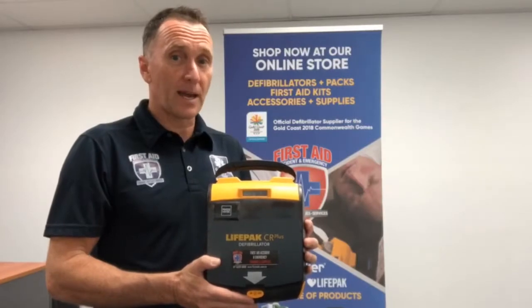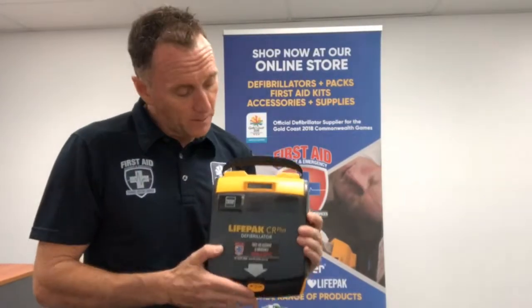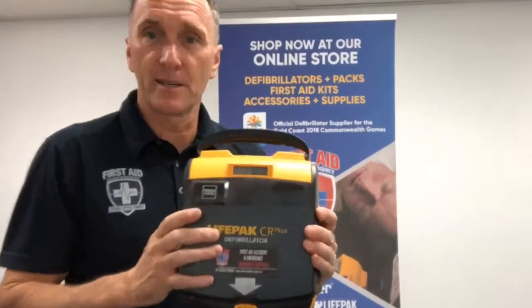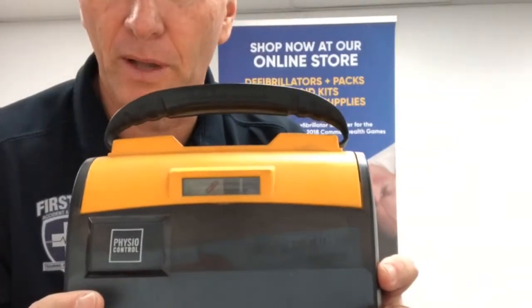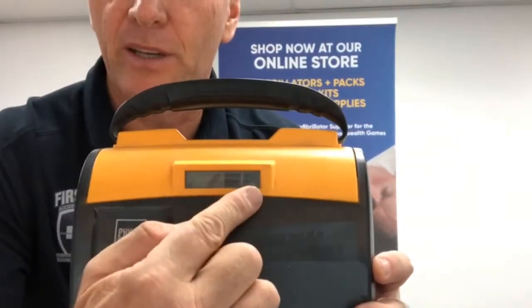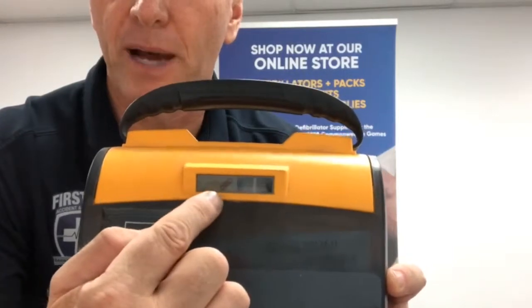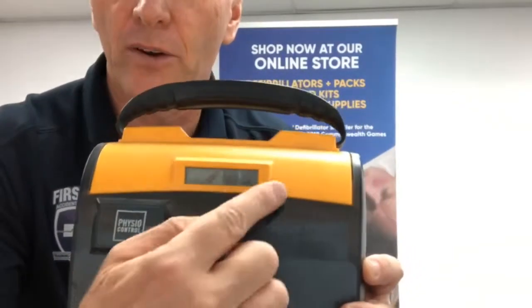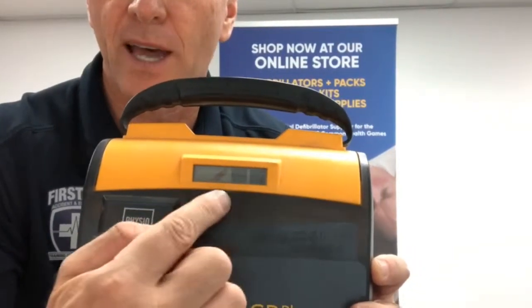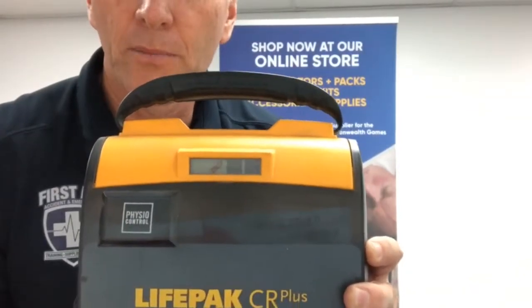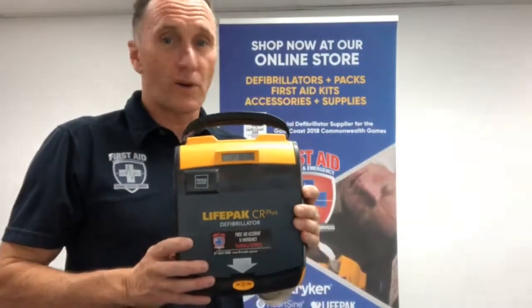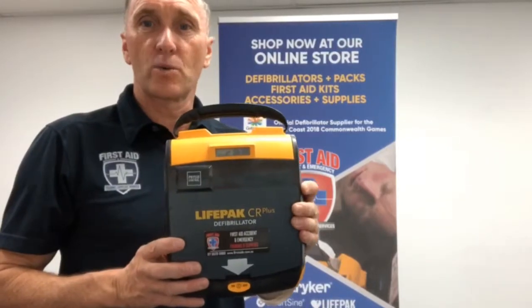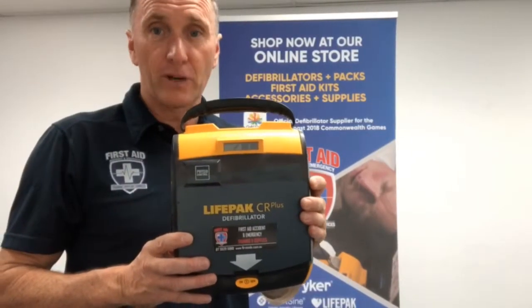You'll know that your pad and battery pack needs replacing by checking the 3 LED indicators at the top of your defibrillator. As you can see on this particular device, we have only 2 dots and a battery symbol. There can be another arrangement where you only have 2 dots and a spanner symbol. In both cases, you need to contact us straight away and we'll organise to send you out a new pad and battery replacement pack.